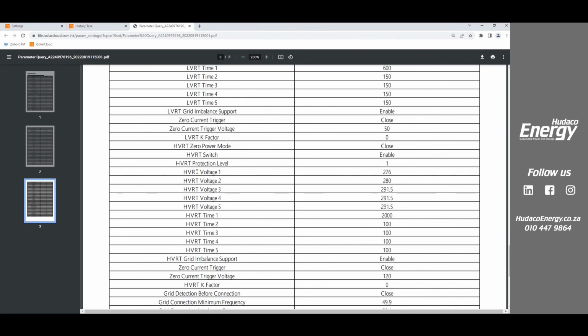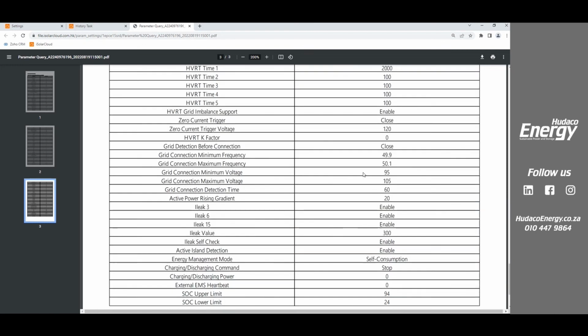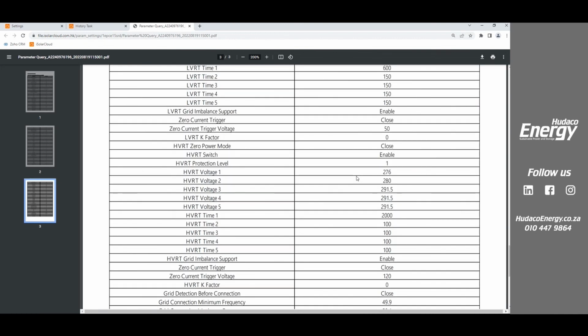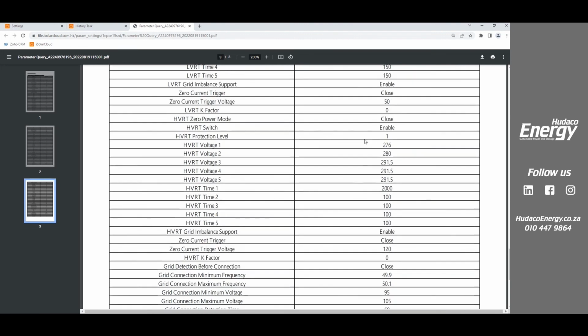My high voltage ride through for NRS comes in at 253 normally. Here we can change this. So I've actually boosted mine up. You can set it anywhere from 260, 270, wherever you want to set it to. And then we set it for, this is in milliseconds. So I've reduced the protection on my own home system. I've put the system at risk, but I know that Eskom is coming to have a look at it.